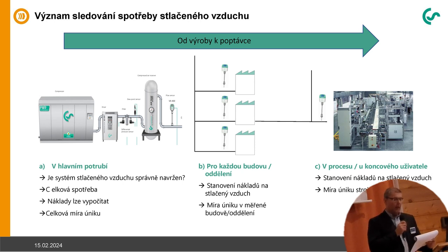So, if you want to measure where your compressed air is going, you have different locations in your factory. On the left side, you can see the generation of the compressed air, the compressor room. There you can measure in the main pipe the total consumption, and you can measure the costs of your compressed air in meters cubed. And of course, you can also see the total leakage rate. So if the factory is stopped during the weekend, you can see on the flow meter how much is the leakage rate in your company. In the middle of the slide, you can see the buildings of the factory, and if you have one flow meter in front of each department, you are able to say in which department how much compressed air is needed. And of course, you can determine and allocate the costs to your departments.